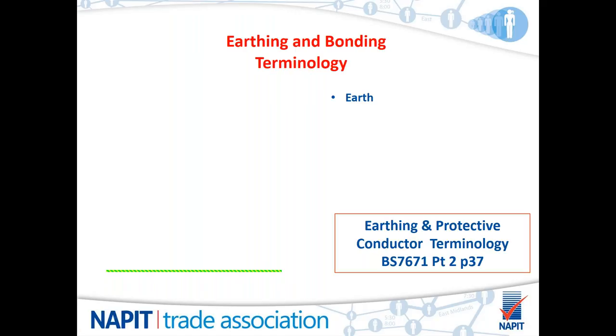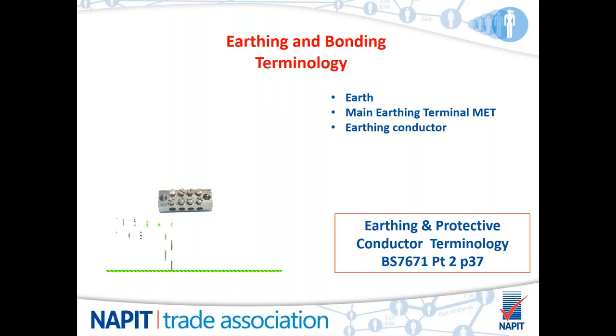This slide is really a little build-up of those terminologies that we've just been going through. The earth, obviously, is the general mass of earth that we sit on. It is a part of the electrical system, and as such, is what we connect all our earthing systems to. As you can see at the bottom there, it does mention the terminology in BS 7671 Part 2 on page 37 that Dave referenced earlier. Just popped up is the main earthing terminal, and connected to the main earthing terminal, you will have your earthing conductor.